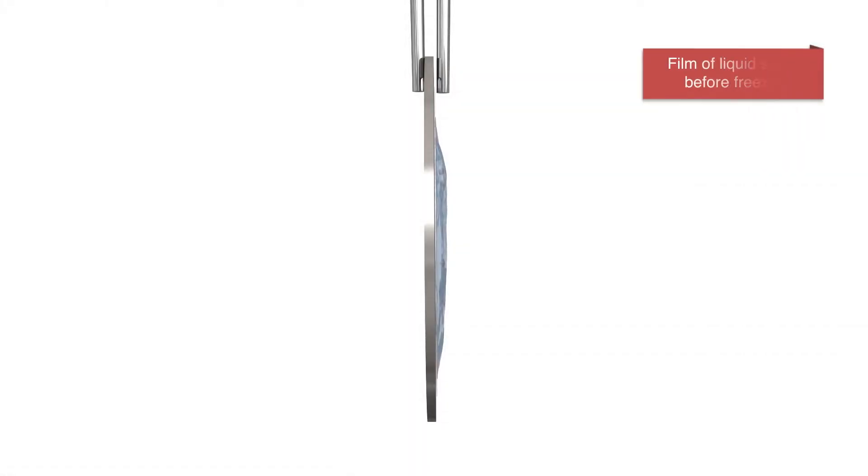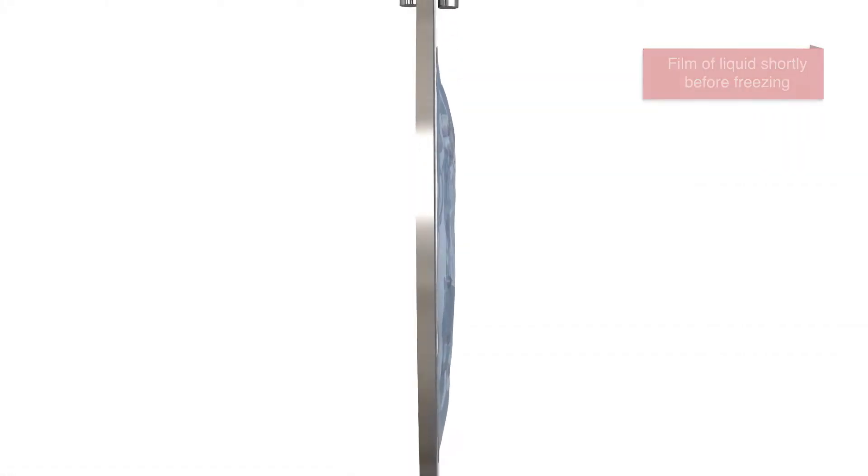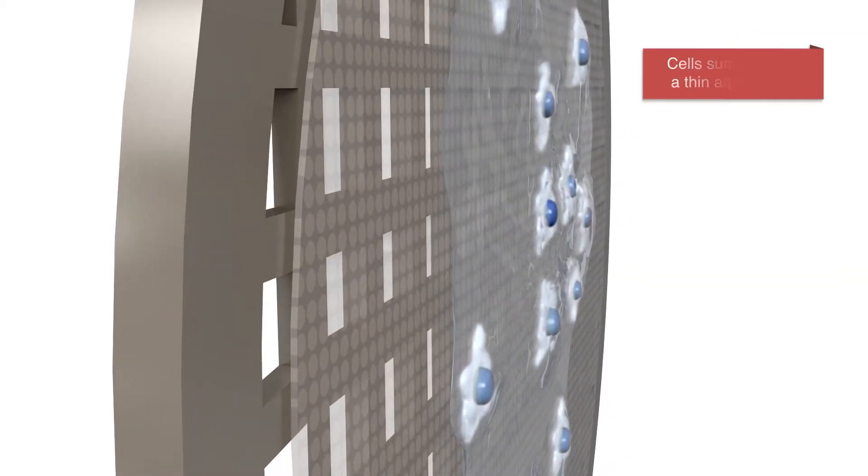To achieve the rapid cool-down of the sample, a thin film of liquid is required. For this purpose, the vitrobot automatically removes excess buffer by blotting the grids.